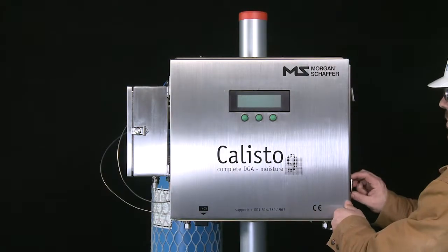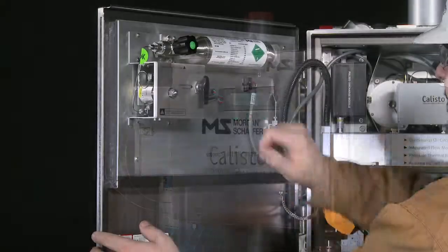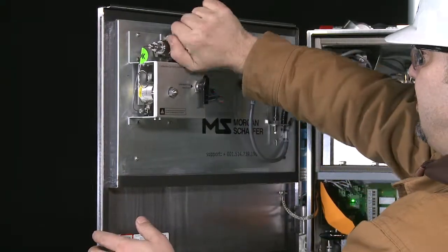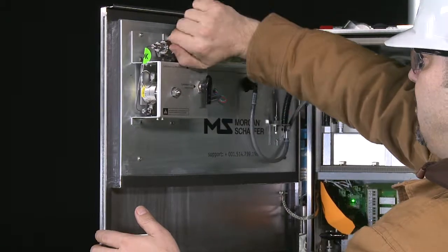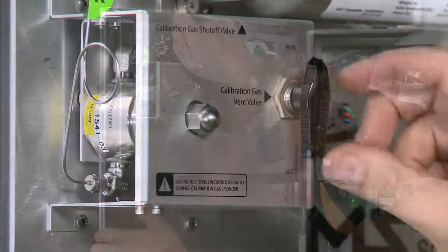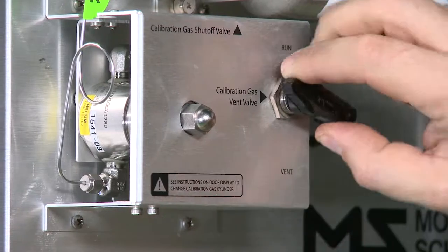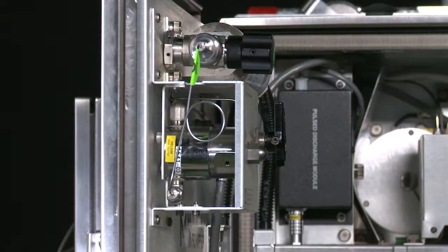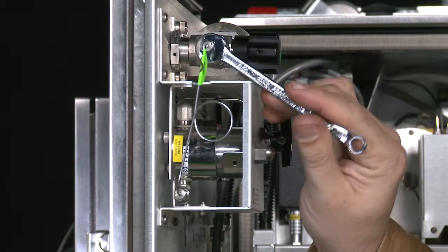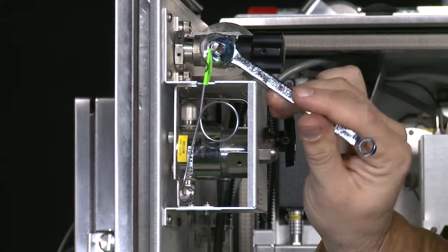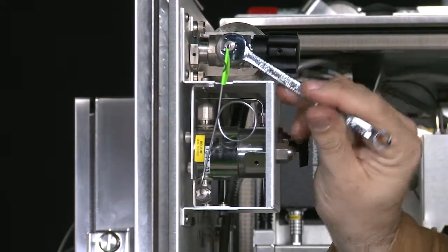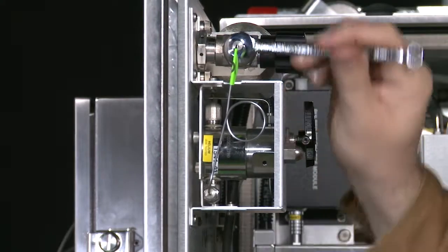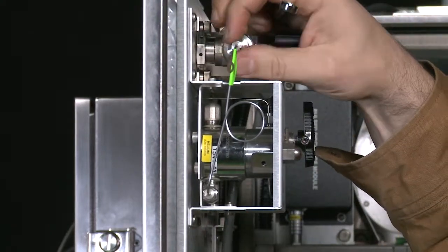Removing the calibration gas cylinder. Open the Calisto door. Close the shutoff valve on the calibration gas cylinder until a moderate resistance is encountered. Turn the module control valve knob to the vent position. Disconnect the fitting from the gas cylinder using a 5/16" crescent wrench and a 9/16" counter wrench on the fitting body to turn the nut counterclockwise. Remove the tube from the cylinder fitting by pulling on the nut.